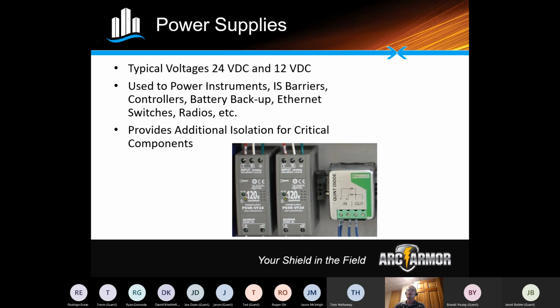the power supply with the DC to DC converter that these power supplies have, and putting a little gel cell type battery out in the field where there's a lot of heat that can be generated, the temperatures can fluctuate a lot. Those type of battery backup circuits work much better than a UPS out in the field, right? If it's outside, if it's in a lift station, it's exposed to extreme temperature changes, UPSs will fail quickly. They're not designed to take the wide variance of temperature.